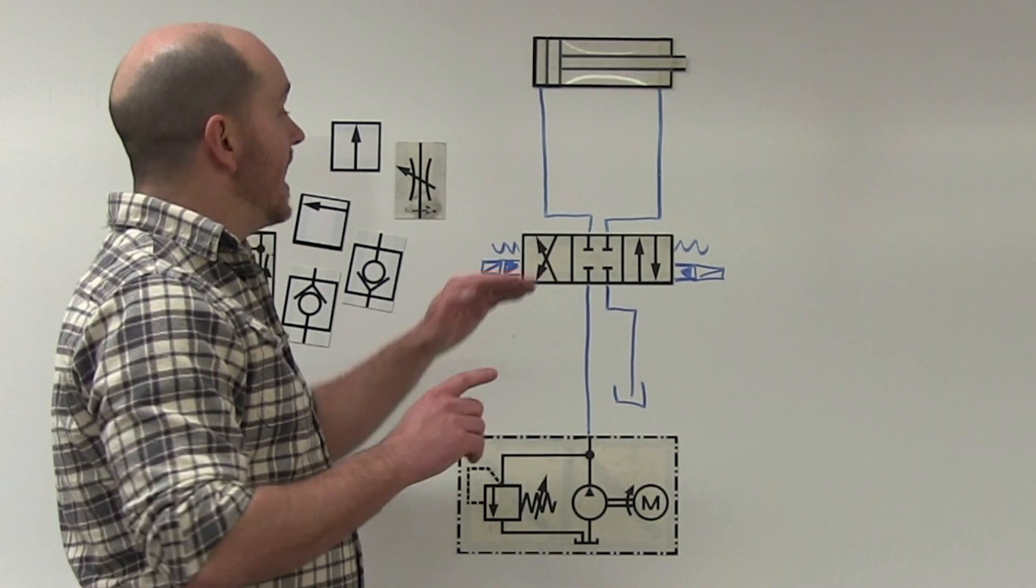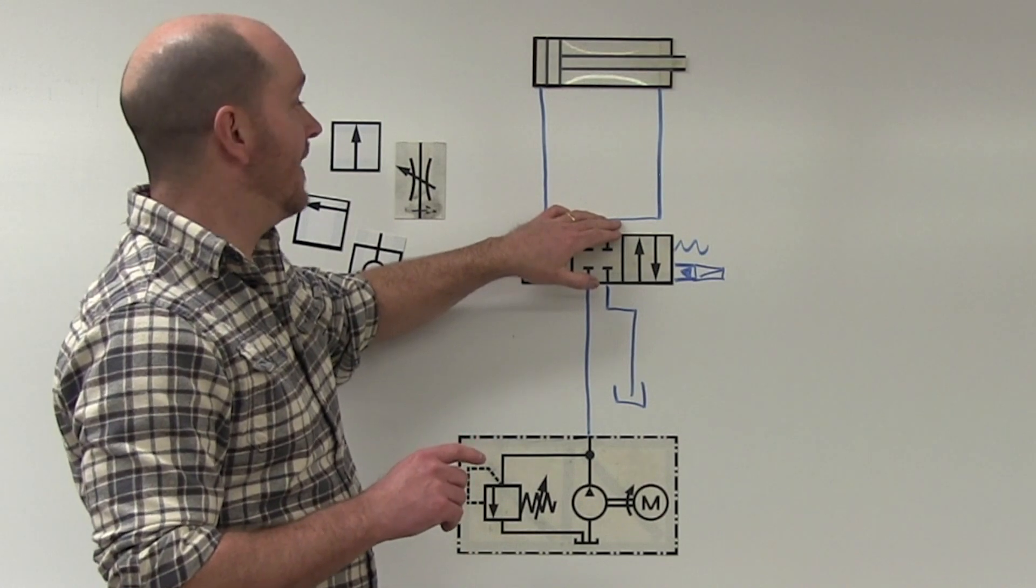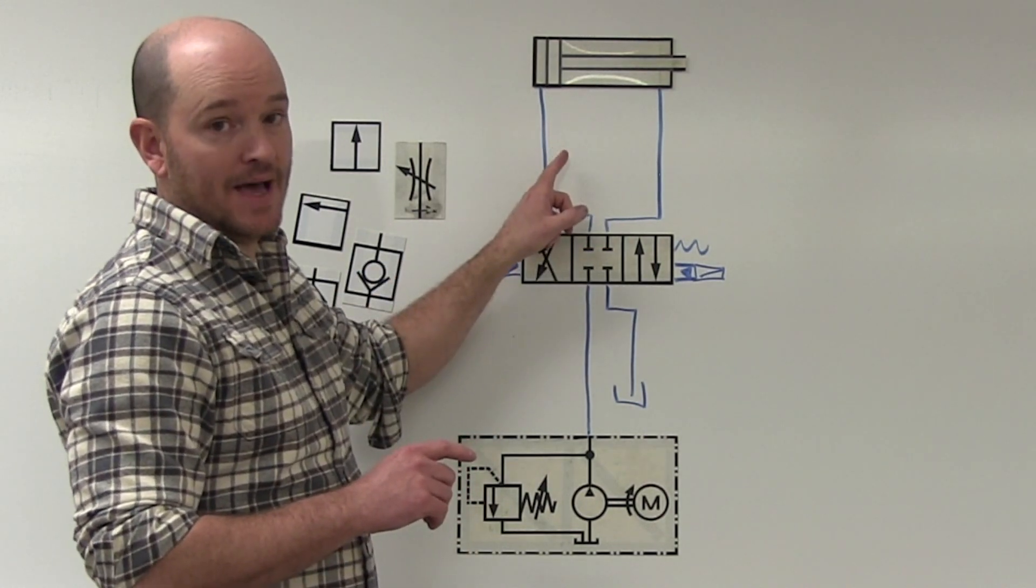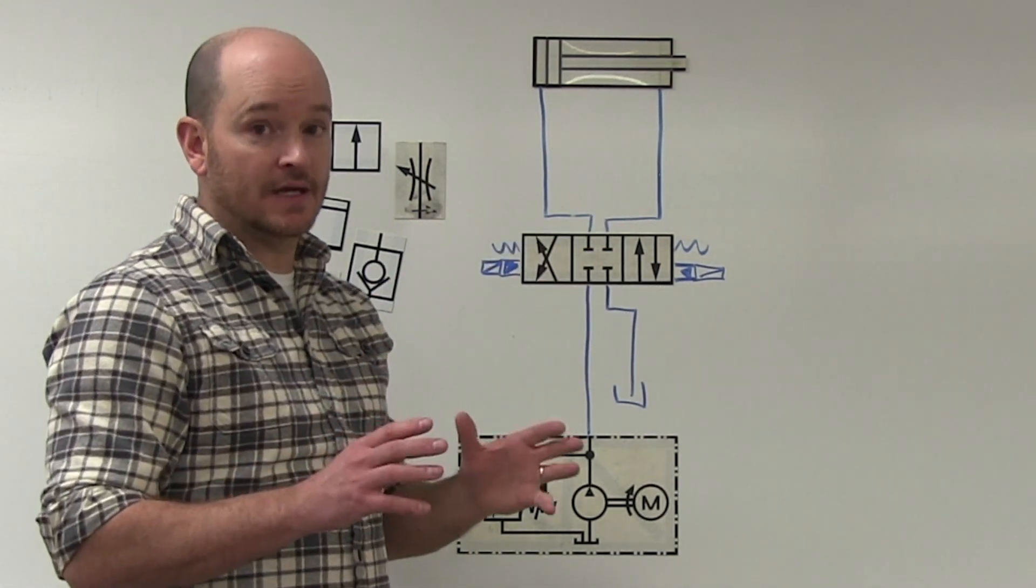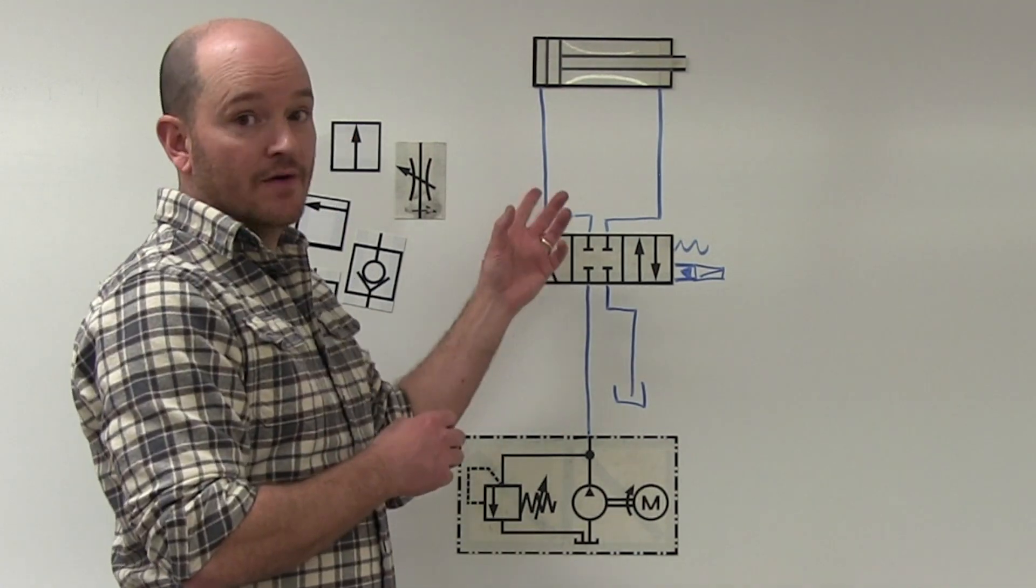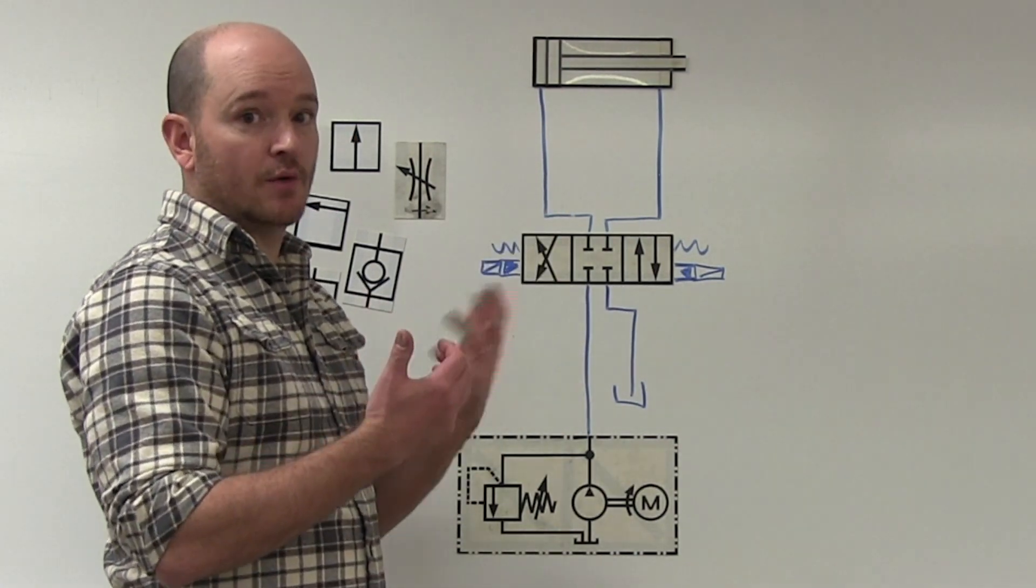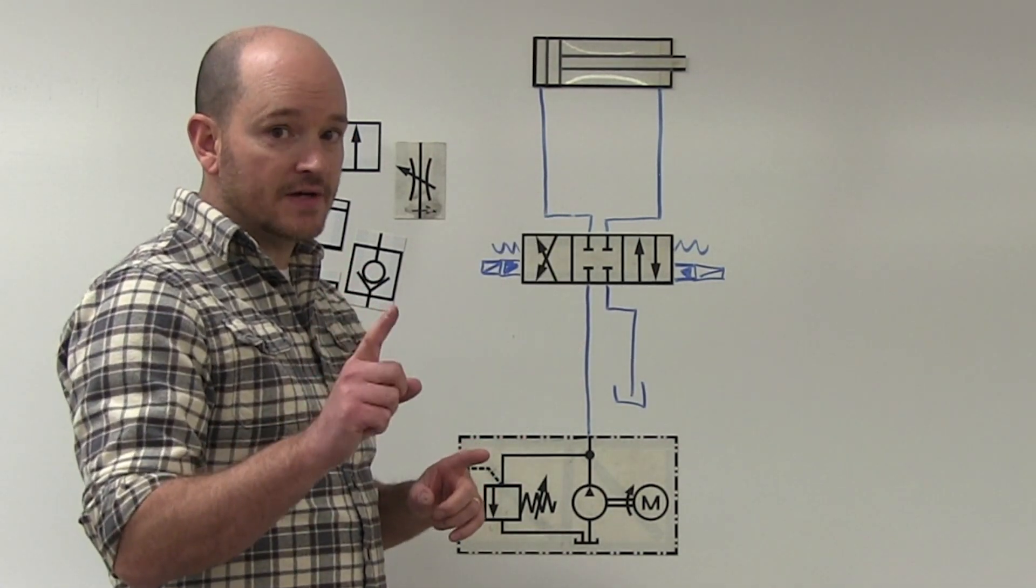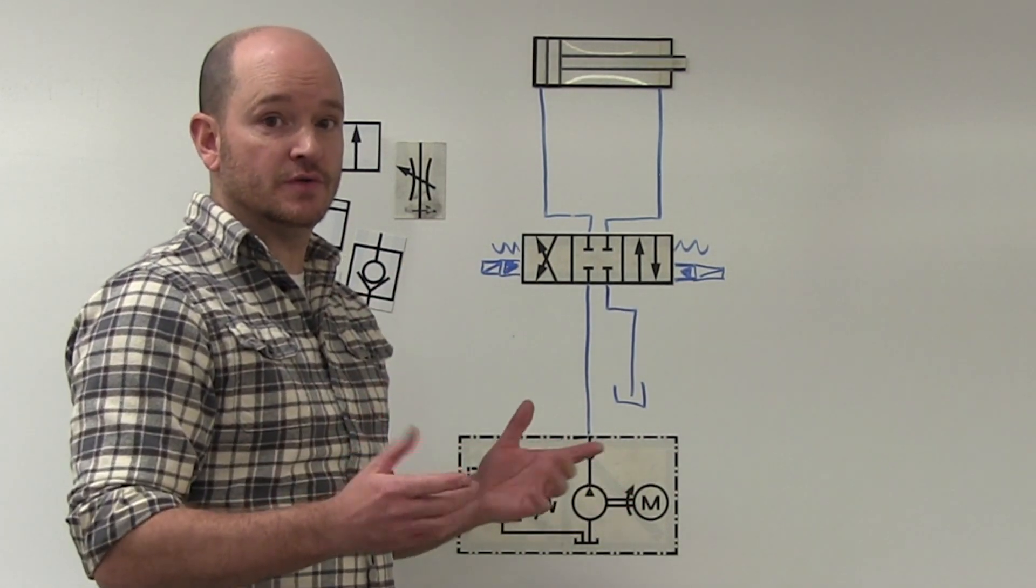If I put it after my directional control valve, I do require a bypass check valve on about 90% of the control valves that I'm going to put in here, so the pressure or flow. And the reason is very simple, but it's very complicated for new students.